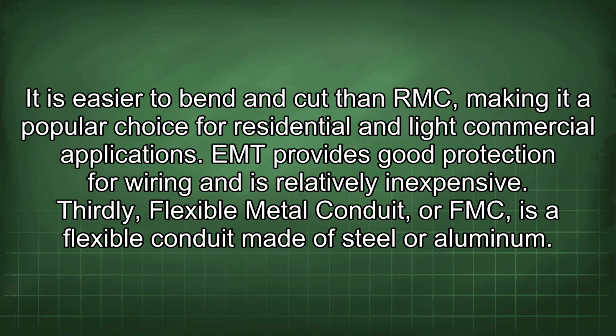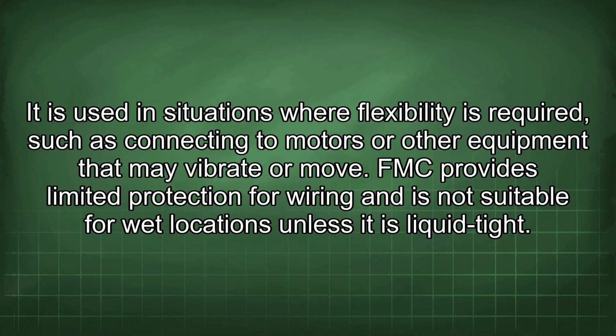Thirdly, flexible metal conduit, or FMC, is a flexible conduit made of steel or aluminum. It is used in situations where flexibility is required, such as connecting to motors or other equipment that may vibrate or move. FMC provides limited protection for wiring and is not suitable for wet locations unless it is liquid-tight.